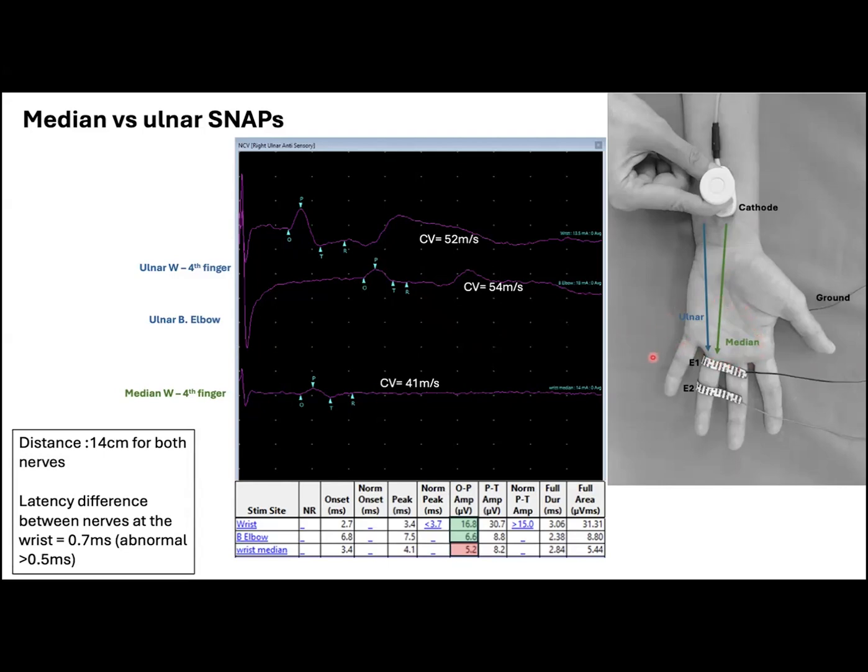To minimize this kind of motor artifact, especially when it starts to obscure the sensory potentials, you could try to use the smallest stimuli possible, to move the recording electrodes away from the muscle that is generating the motor response, let's say by placing the recording electrodes at the proximal interphalangeal joint, or by asking the patient to spread the fingers, or even by protecting the electrodes with gauze.